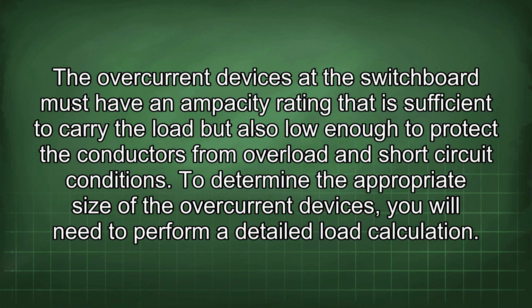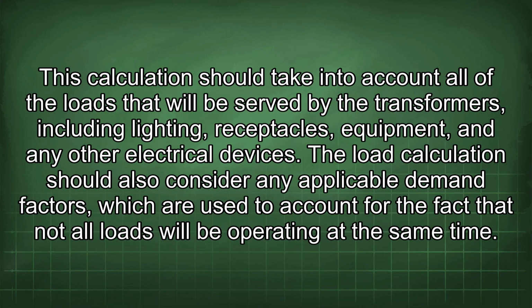To determine the appropriate size of the overcurrent devices, you will need to perform a detailed load calculation. This calculation should take into account all of the loads that will be served by the transformers, including lighting, receptacles, equipment, and any other electrical devices. The load calculation should also consider any applicable demand factors, which are used to account for the fact that not all loads will be operating at the same time.